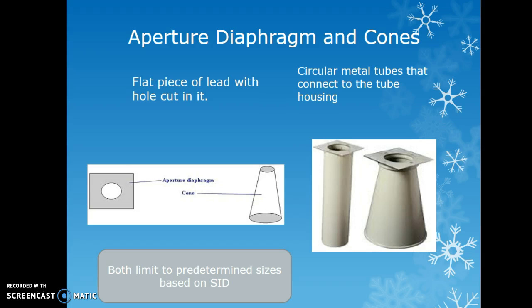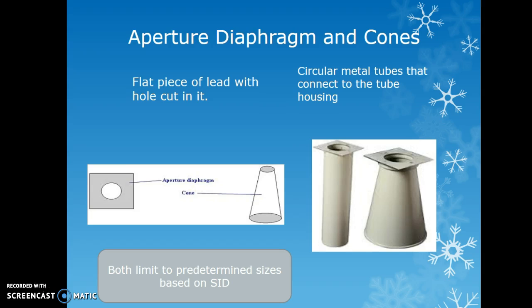An aperture diaphragm is a flat piece of lead with a hole cut in it. Cones are circular metal tubes that attach to the tube housing and produce circular collimation. Based on the SID, the opening will be larger or smaller depending on the distance from the patient. These are used for head work such as sinuses, nasal bones, and TMJs, but are not commonly seen today.